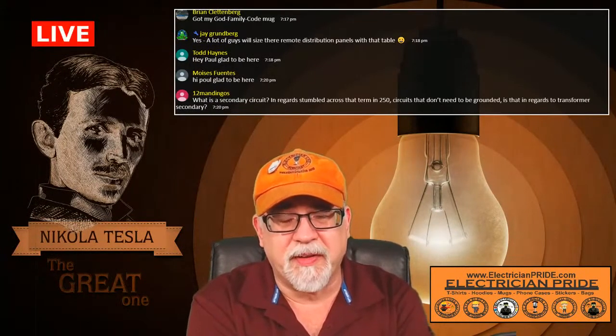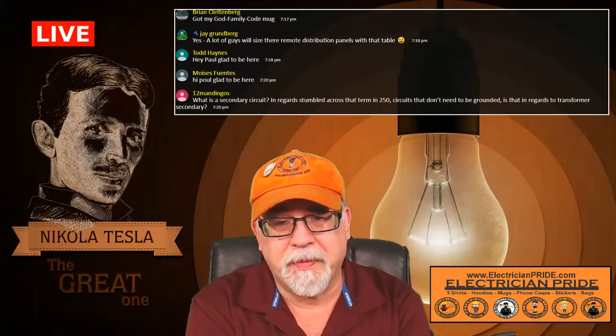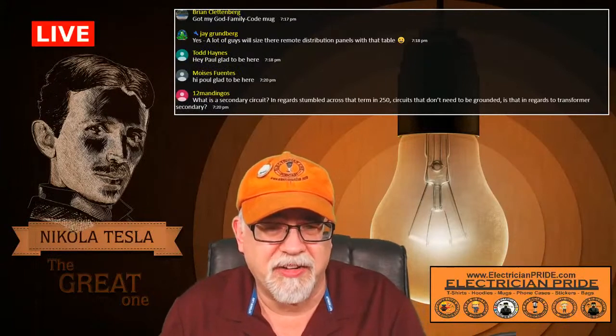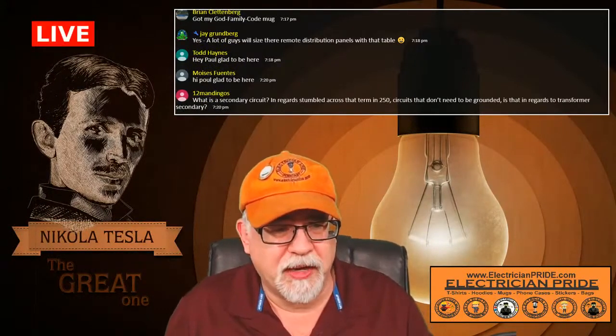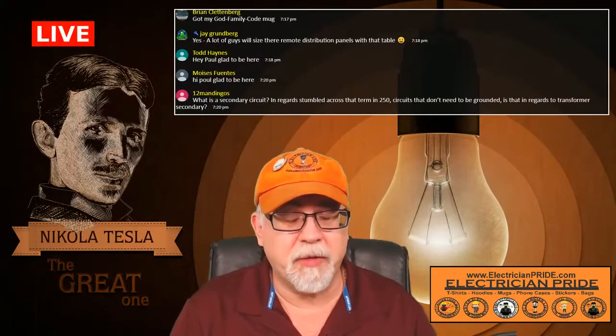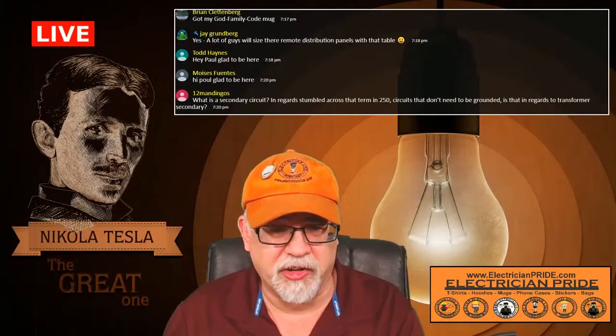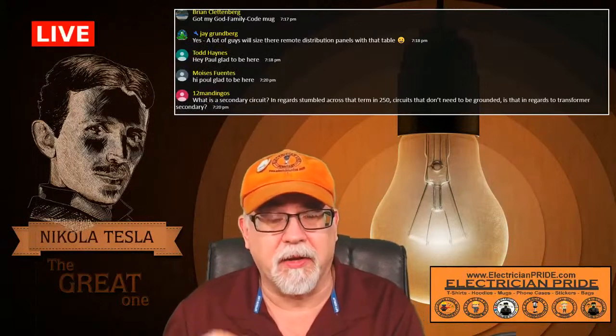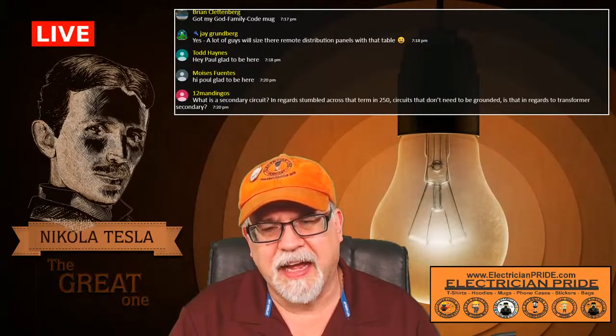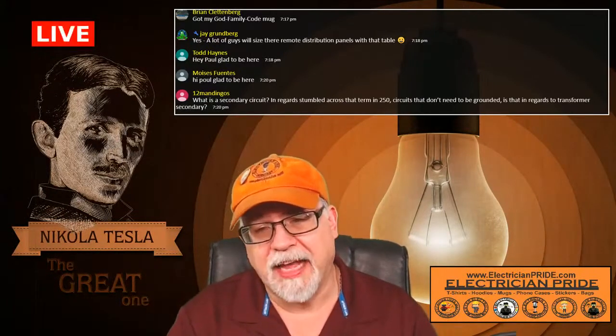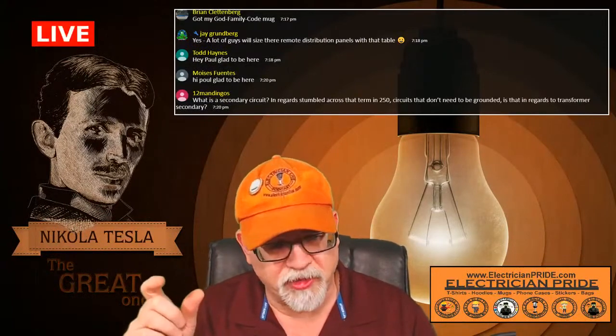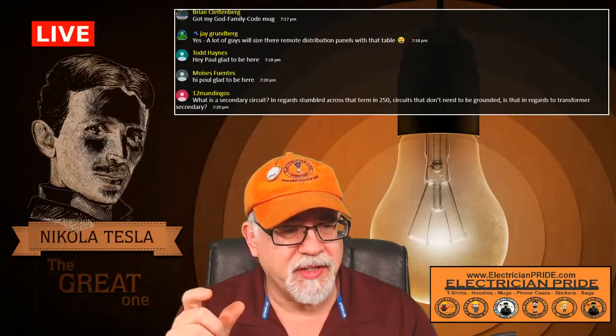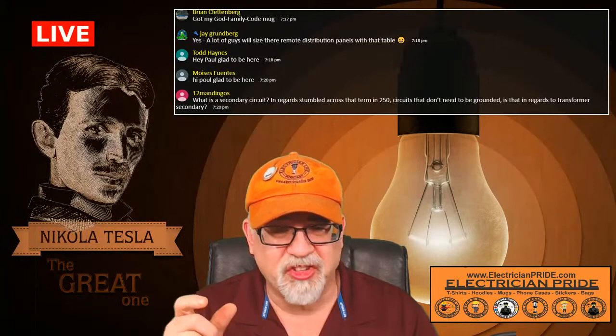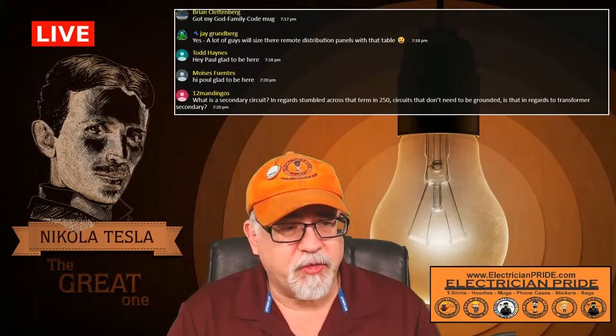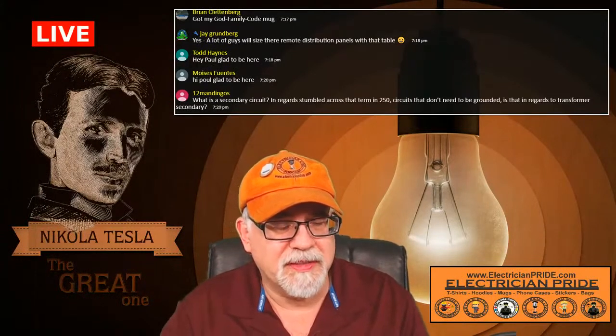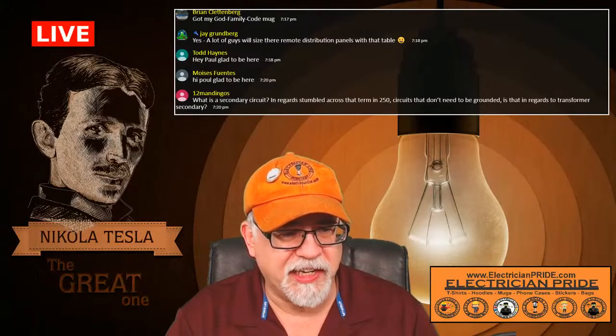Secondary conductors, even coming from a secondary of a transformer in grounding and bonding, wouldn't be an equipment grounding conductor - it'd be a supply side bonding jumper, because it's going from the transformer all the way up to the first overcurrent device. It could be in a fixed metal raceway like EMT, then you don't need a conductor in there. But if it's not fixed metal, you'd have to put in a supply side bonding jumper that runs all the way up there. And of course, the system bonding jumper can be either in the transformer or in the first disconnecting means. So I'm not 100% sure about your exact question, you'd have to tailor it down, but when we talk about secondary circuits, a secondary of a transformer means secondary conductors from the transformer. I'm not 100% sure what you might be talking about, so dig a little deeper.